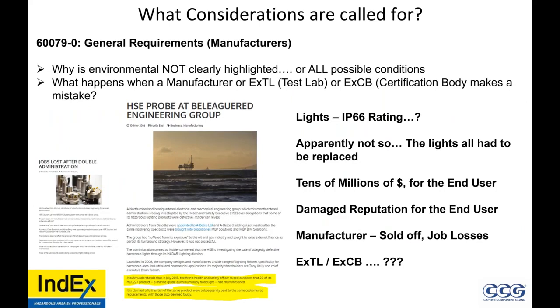Well, a manufacturer was found that their lights did not meet IP66. So what happened? The end user lost tens of millions of dollars and had a damaged reputation. The manufacturer was just sold off to another manufacturer, with a couple of job losses. Now, water getting into it, it's unsafe. What happened to the testing laboratory and the certification body of those lights? Did they test them right? Did the manufacturer do something incorrect after the fact? The point is the lights manufacturer went under and was sold off, and people lost their jobs. And this affected many projects for tens of millions of dollars because the IP rating was not as it was said to be.